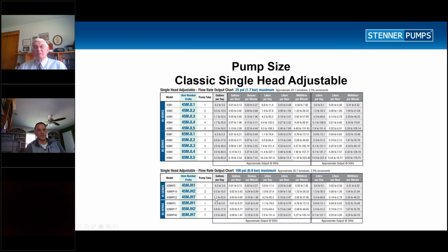So what you're always trying to do is size the pump and select the tube as close to your max flow output as possible. We recommend running our pumps with adjustable feed rate controls at settings of 5 or higher. The closer you can get to 100%, the better. There are many times I go out in the field and see customers running pumps at 1, 1.5, and 2, and very quickly the feed rate controls will start wearing out in 3, 4, 5, and 6 months, because the pins in the feed rate control, as we will show you in a video, rise and fall frequently on the index plates.